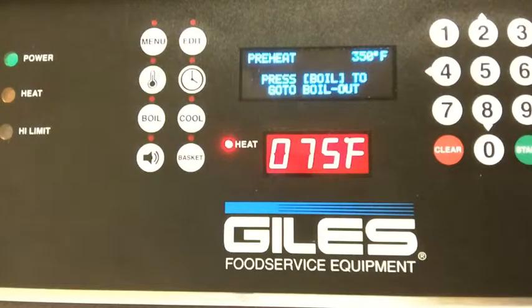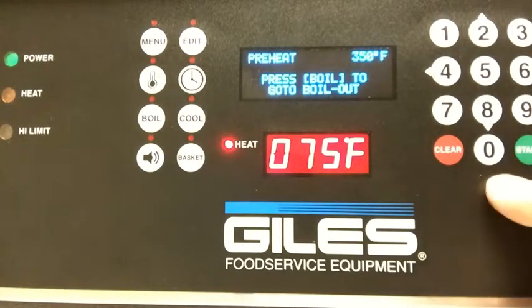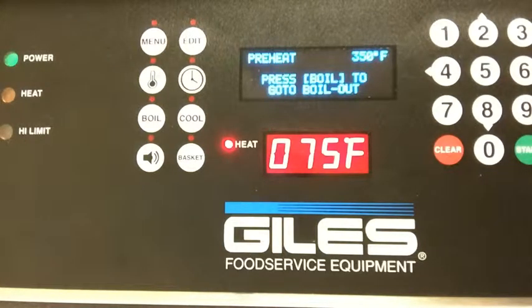Sometimes during the morning when you try to fire the unit up, if you have extremely cold oil, the oil will heat in a certain area and get above that temperature, and it'll give you error messages like that every once in a while. But by just stirring the oil and pressing the start button, it'll clear it and you'll be able to get beyond it. But that is a safety, just like having the drain valve switch to keep them from firing the unit up if the oil gets too low.